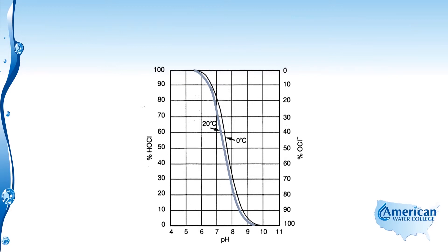We're going to look at the 20 degrees Celsius temperature line and see what happens when the pH of the water is 8. A pH of 8 is typical for water systems. At a pH of 8, we see that 20 percent of the chlorine is in the form of hypochlorous acid.